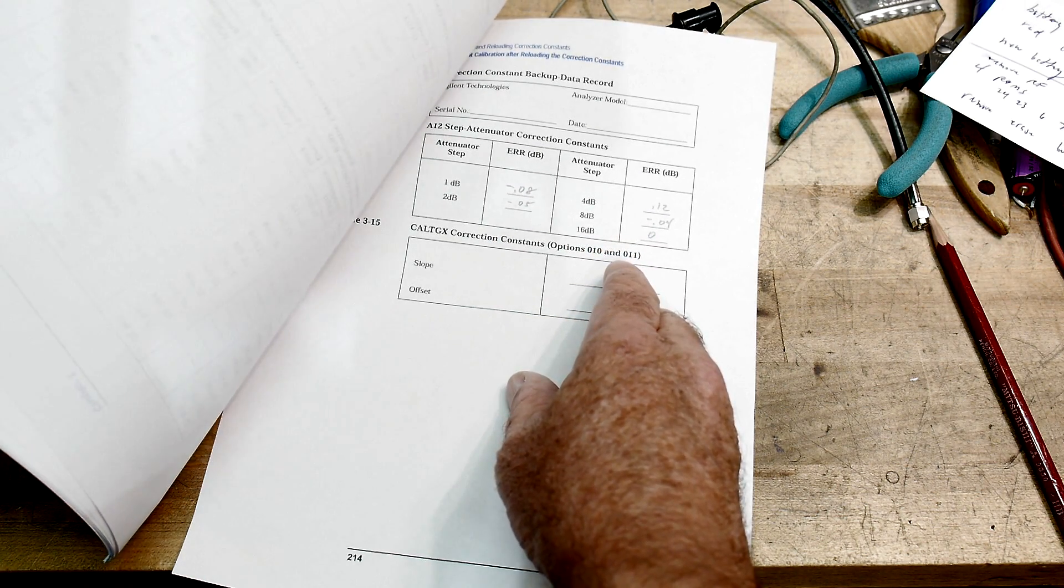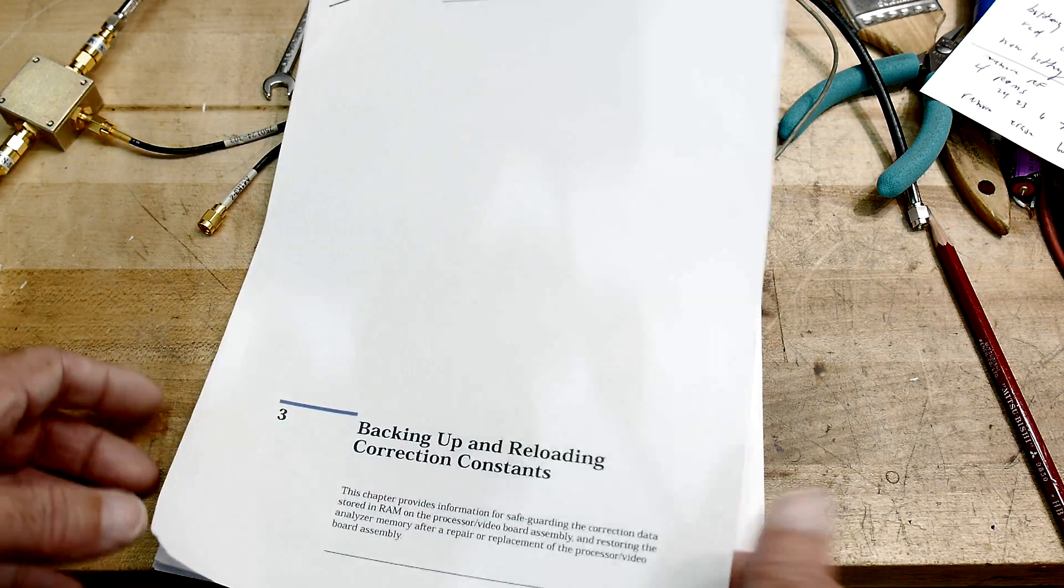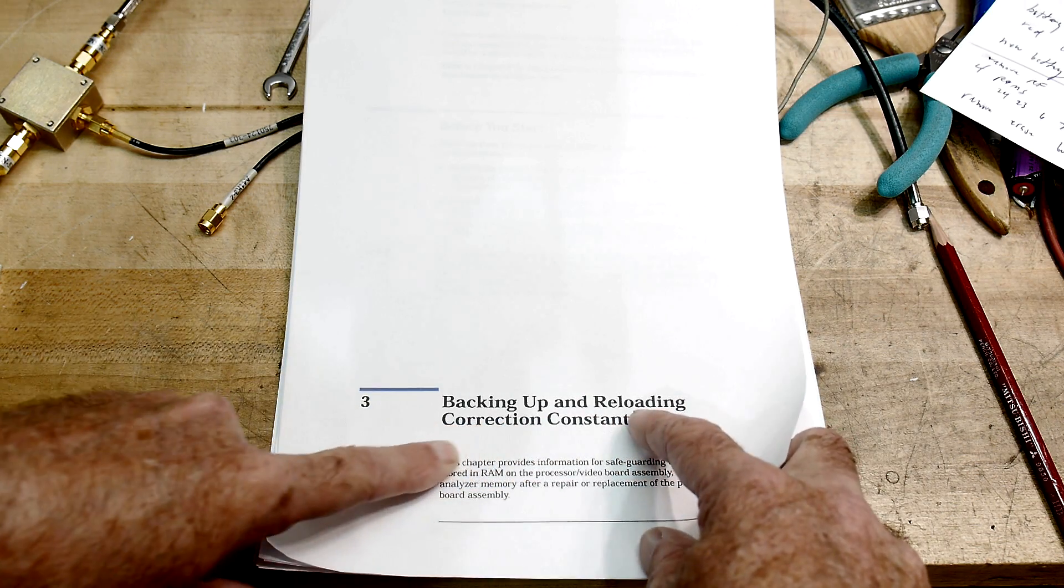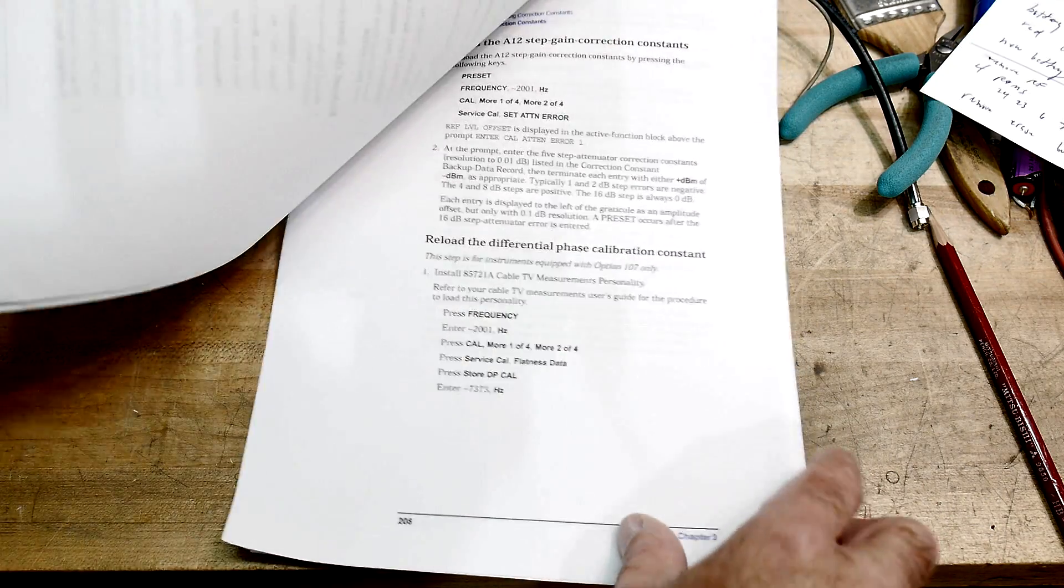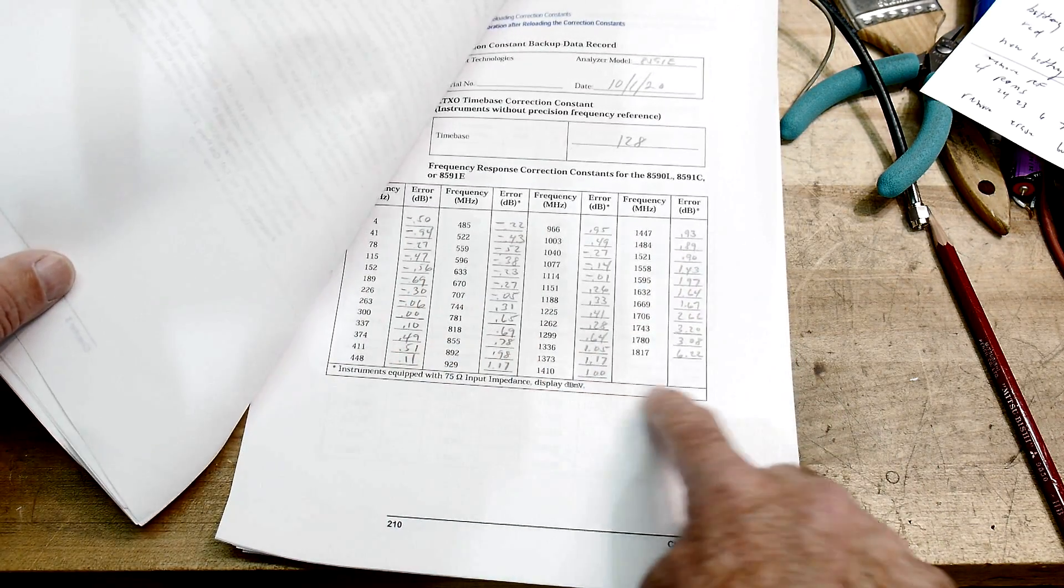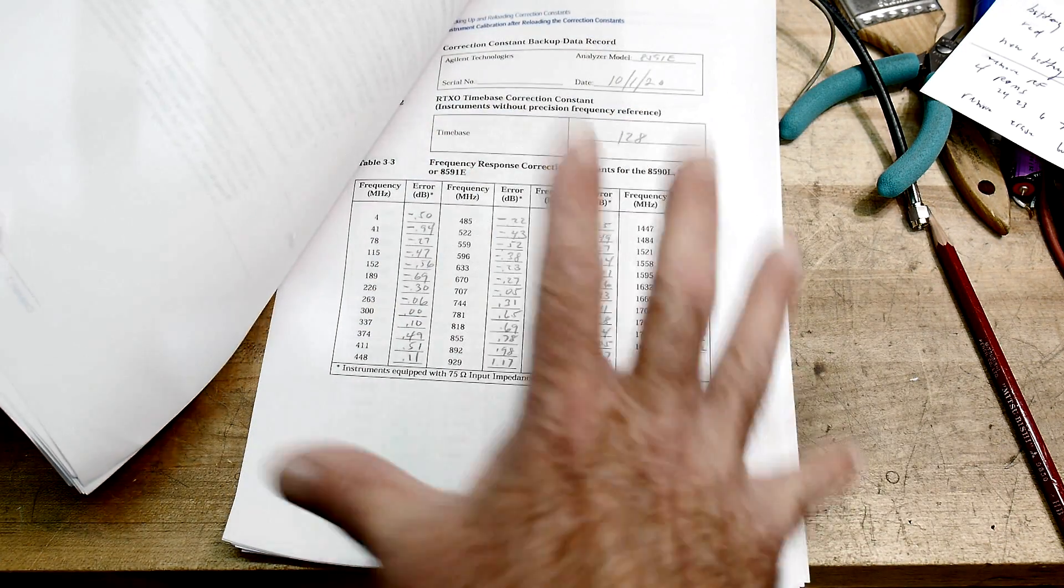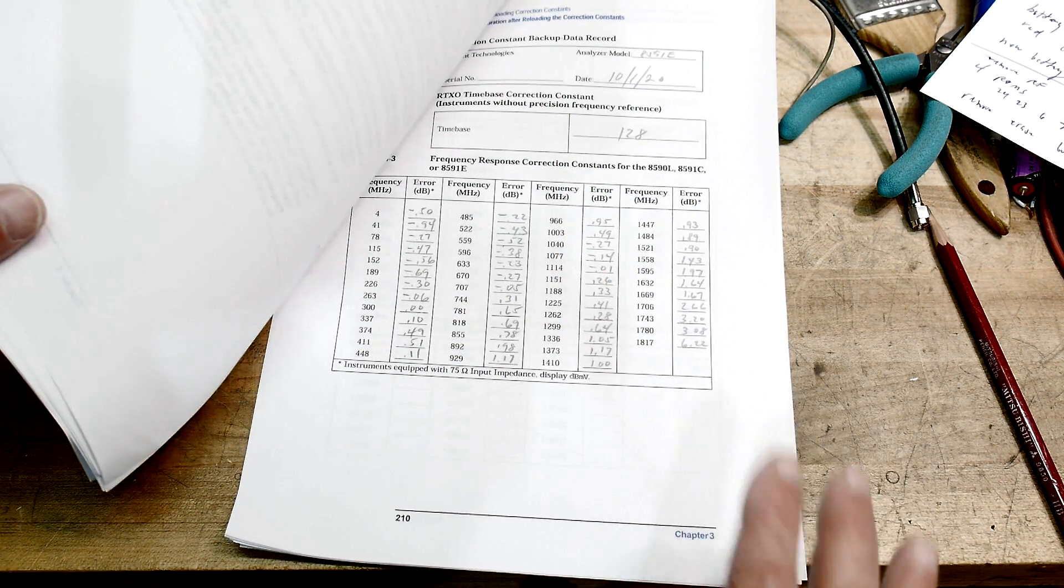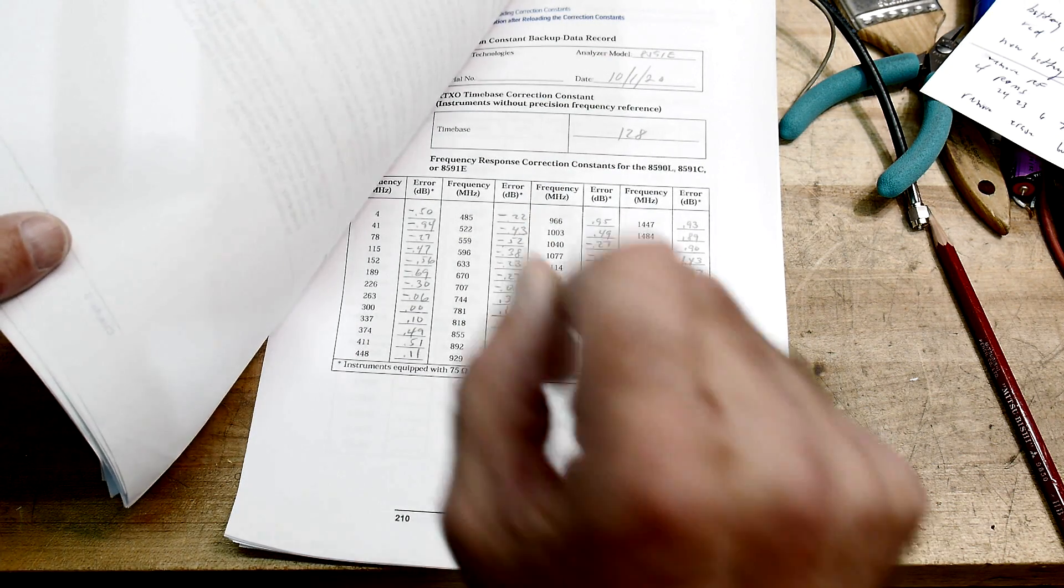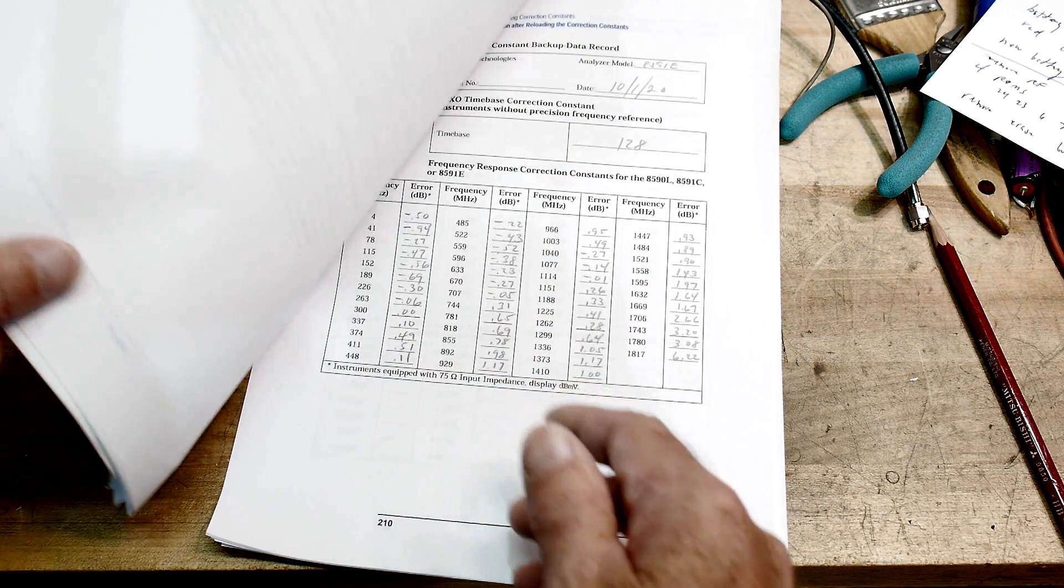Now, when I bricked my instrument and turned it back on and it erased everything for me, then you'd have to do the reloading section. So there, again, you go through this document. It tells you how to reload. And then you go to yours. And you actually have to type these all back in. You type them all back in. It tells you exactly how to do all this. And then once you get them all in there and you do a save, then you need to calibrate the instrument. So you have to push the CAL button and wait nine minutes and come back and save that. So you have to do two saves, one save for the edits and then one save for the calibration.